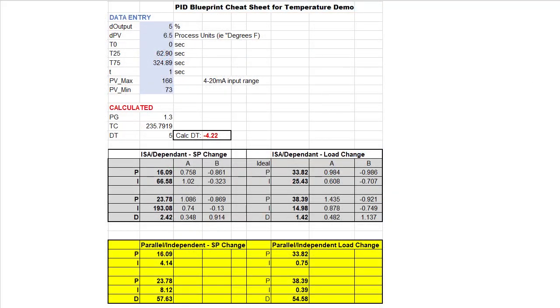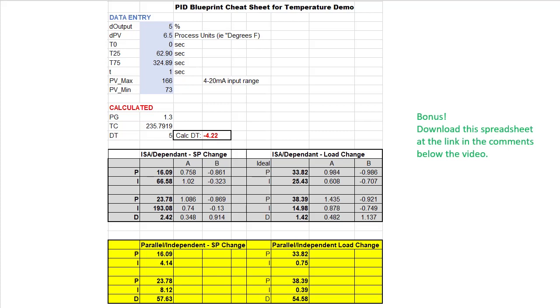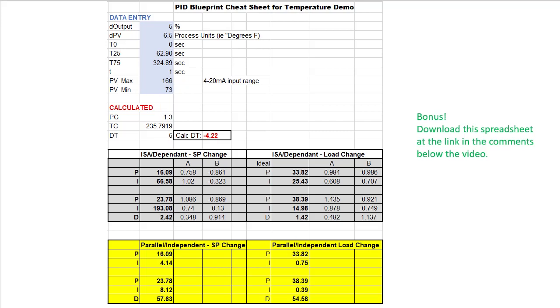I put those formulas into a spreadsheet to make it super easy for me to play with. I just enter the measured data here and that automatically falls right through to the PID coefficients we need. Notice that the calculated dead time is here, but since that was a problem, I put our measured dead time in here.